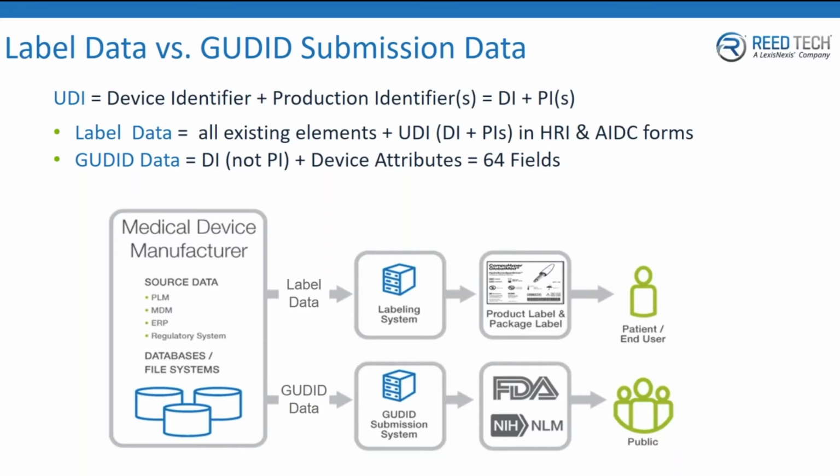The other data flow, which is on the lower row, is brand new, and this is something that has not been implemented in the past. So when UDI requires it, you'll need to create a procedure, pathway, means to collect UDI information, build the particular messaging, send it to the regulatory bodies, in this particular example, the FDA, so that you do meet the regulatory requirements.